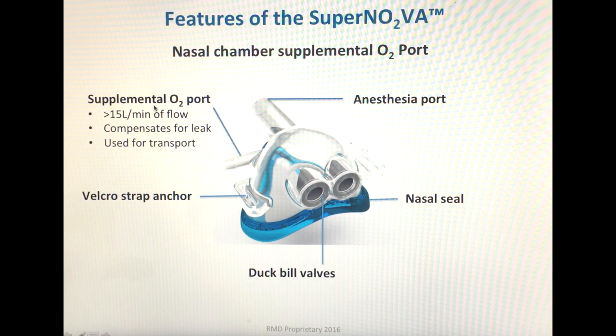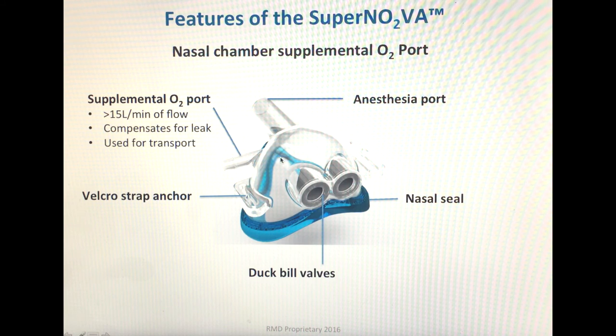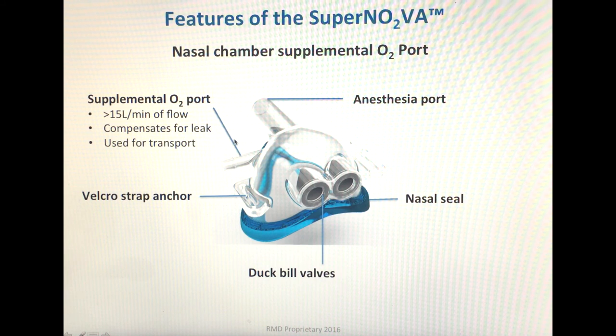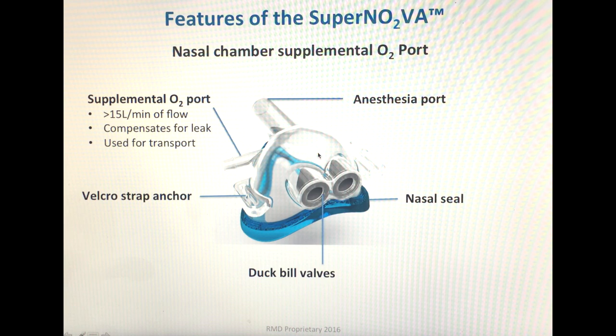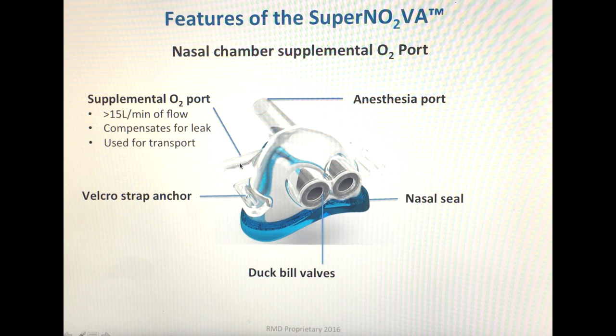The SuperNO2VA also has a supplemental oxygen port, which serves two functions. First, it allows an additional 15 liters of oxygen to flow into the mask — useful if a patient has an excessive leak out of the mouth, allowing compensation for that leak by adding additional flow. The second function is that it can serve as a supplemental oxygen mask for transport. Rather than switching to a nasal cannula or oxygen face mask at the end of the case, you simply connect oxygen tubing to the SuperNO2VA's supplemental oxygen port to transport the patient to PACU.